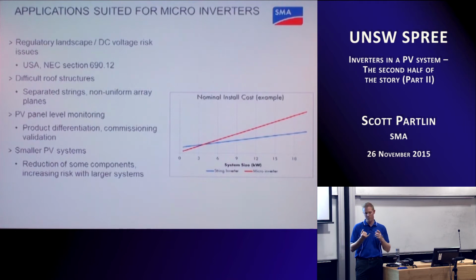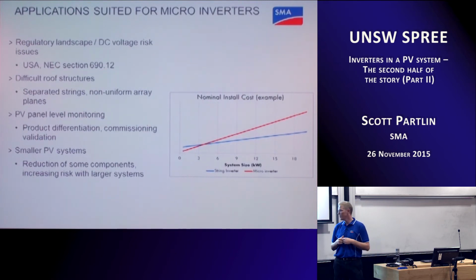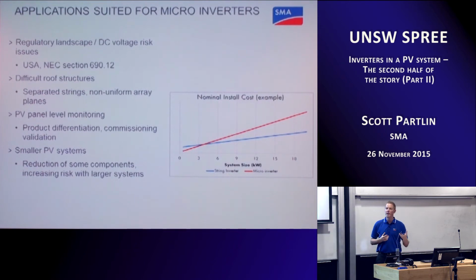So you don't have to buy DC cabling. You don't have to install DC isolators. Within an Australian context, you don't have to buy heavy duty conduit to put the DC cabling in. So you're able to avoid some of those costs when you use a microinverter system. The drawback of microinverters, though, is that, like a string inverter, they are an inverter and they have about the same number of components as a string inverter, actually a little bit less. And so there is an inherent cost in that unit.